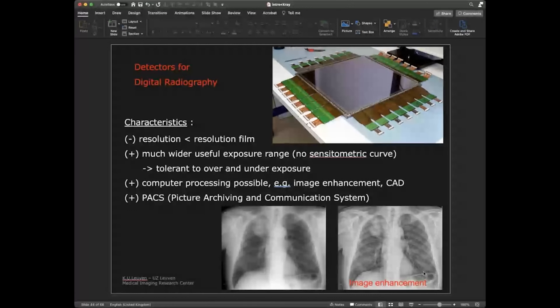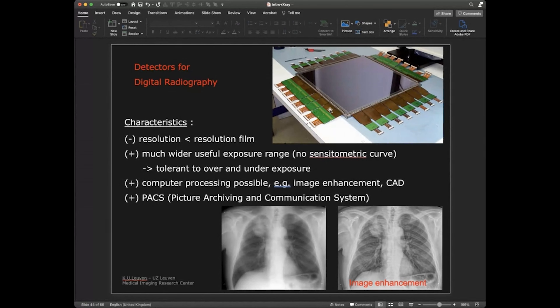Currently, digital detectors are increasingly used instead of phosphor screens — silicon-based chips where X-rays interact with the detector and generate electrons locally, similar to a CCD camera but sensitive to X-rays. The advantages are that this is digital, smaller, and much more controllable.